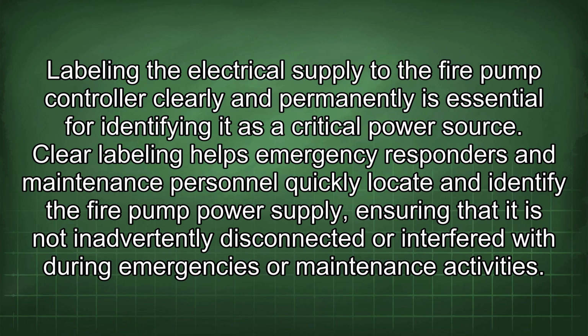Labeling the electrical supply to the fire pump controller clearly and permanently is essential for identifying it as a critical power source. Clear labeling helps emergency responders and maintenance personnel quickly locate and identify the fire pump power supply, ensuring that it is not inadvertently disconnected or interfered with during emergencies or maintenance activities.